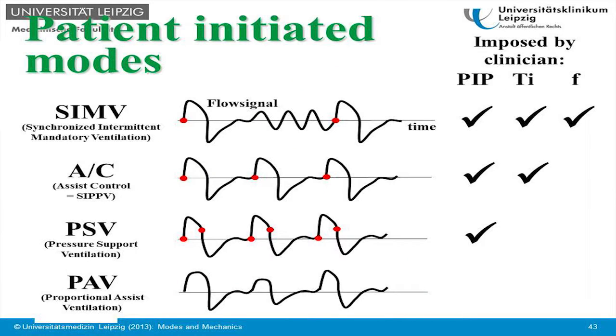So we have a lot of patient-initiated modes available with newer machines, made possible by the different sensors that are included in the modern ventilators. I have a comparison here, SIMV. The clinician still is setting the peak inspiratory pressure, the inspiratory time, and the frequency. The patient has only control about the timing of his ventilation.